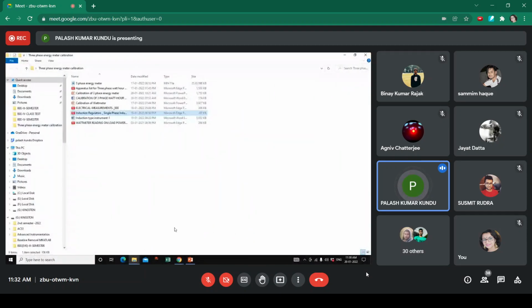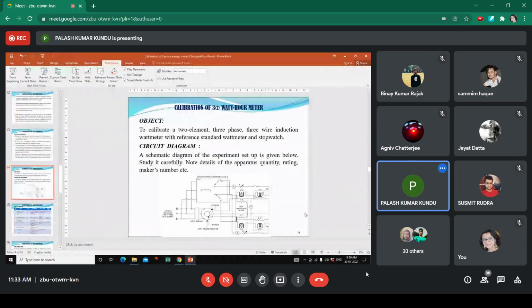The same principle is utilized here. This is a three-phase phase shifter. This is the symbol of the induction regulator type phase shifting arrangement. So what will happen? Basically, according to the dial of the phase shifter, the phase difference angle between the load current, that is according to the phantom loading circuit, and the voltage applied to the pressure coil of both the wattmeter and the standard energy meter can be varied.